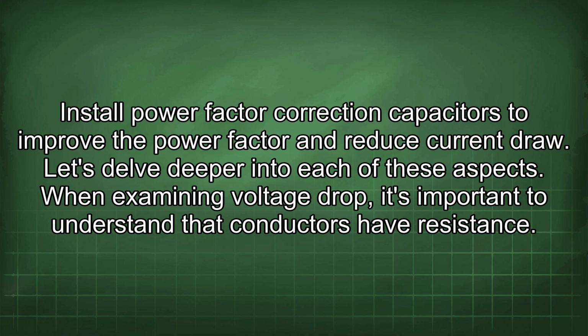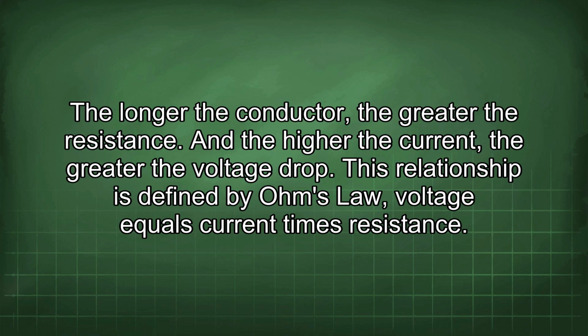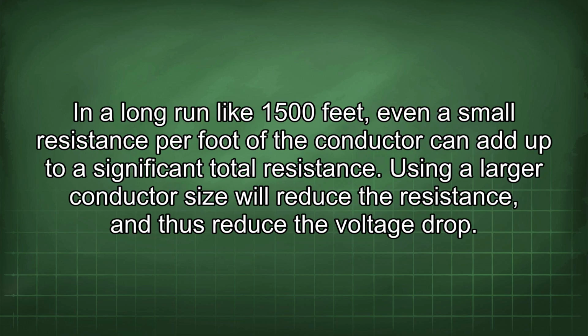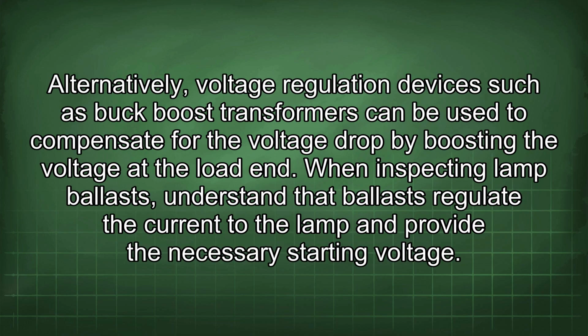Let's delve deeper into each of these aspects. When examining voltage drop, it's important to understand that conductors have resistance. The longer the conductor, the greater the resistance. And the higher the current, the greater the voltage drop. This relationship is defined by Ohm's law: voltage equals current times resistance. In a long run like 1500 feet, even a small resistance per foot of the conductor can add up to a significant total resistance. Using a larger conductor size will reduce the resistance, and thus reduce the voltage drop. Alternatively, voltage regulation devices such as buck-boost transformers can be used to compensate for the voltage drop by boosting the voltage at the load end.